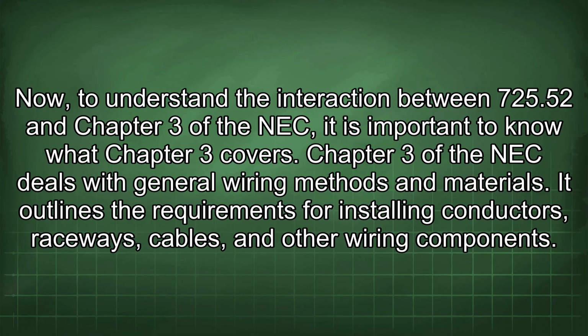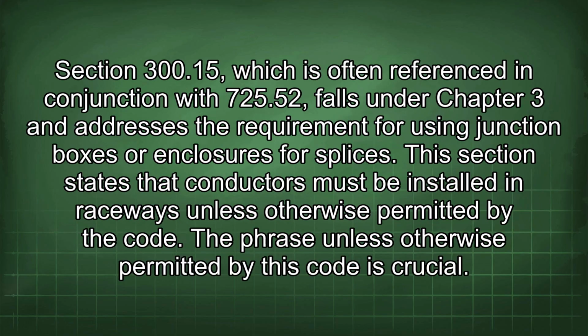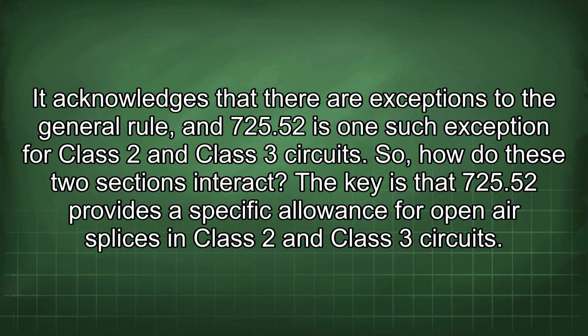Chapter 3 of the NEC deals with general wiring methods and materials. It outlines the requirements for installing conductors, raceways, cables, and other wiring components. Section 300.15, which is often referenced in conjunction with 725.52, falls under Chapter 3 and addresses the requirement for using junction boxes or enclosures for splices. This section states that conductors must be installed in raceways unless otherwise permitted by the code. The phrase "unless otherwise permitted by this code" is crucial. It acknowledges that there are exceptions to the general rule, and 725.52 is one such exception for Class 2 and Class 3 circuits.